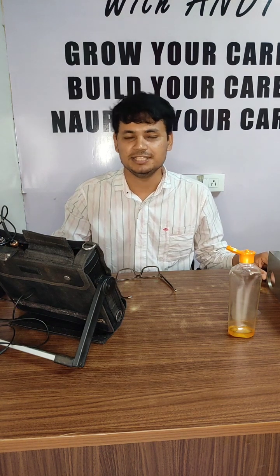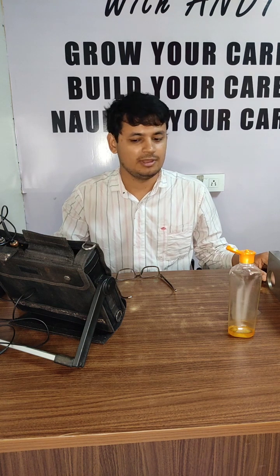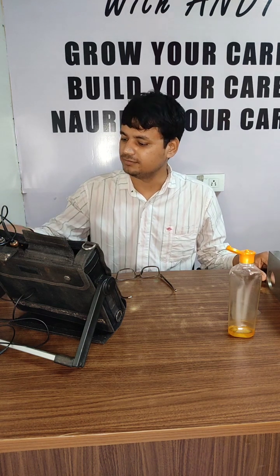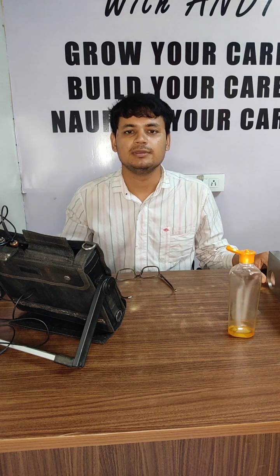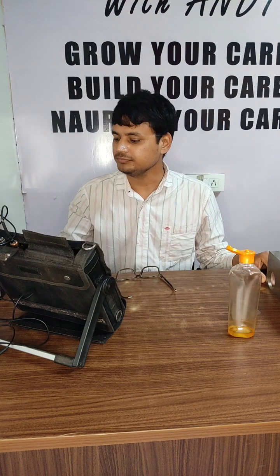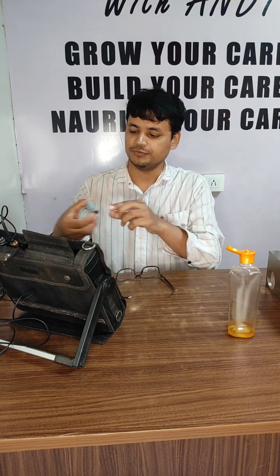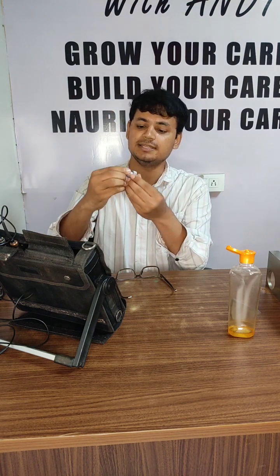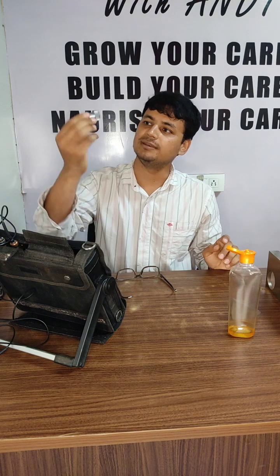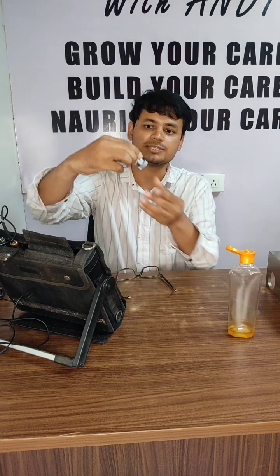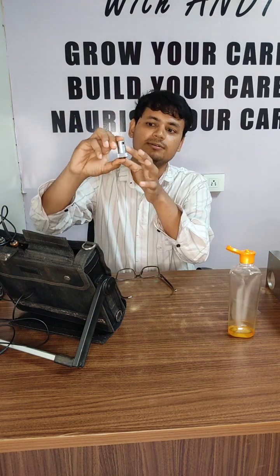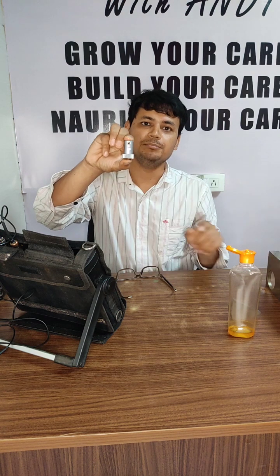We have an ultrasonic machine. The name of the machine is DigiScan DS324. Along with this machine we have various kinds of probes. Basically there are three types of probes. First is the normal probe, which looks like this. There is a piezoelectric crystal inside this probe, which you can imagine is in between this casing. There is only a single socket, which you can see here. It's called mini LEMO.